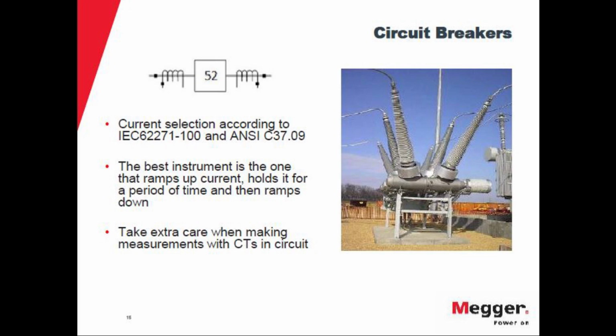When testing circuit breakers, there are standards that guide what to do and how to do the test. Especially on dead tank breakers that have the CTs mounted on the bushings, because everything is connected to the protection system. If you have a very high current change here, the protection will trip. Even though it's an offline test, the protection is still connected, and you might trip the breaker because of the current, because the CTs are connected there. So you want to use an instrument that has a very soft ramp and doesn't affect the protection system. And you also want a very clean signal, so you don't have high ripple.